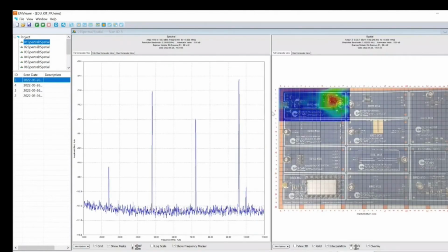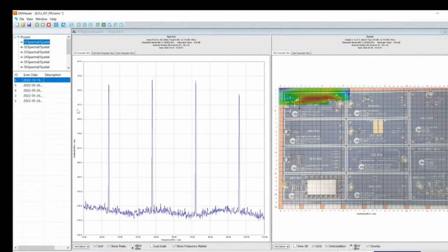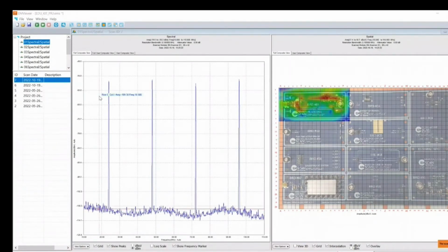And that's the software. This is the scan itself, that experiment that I did just before. Again, I can run the scan now, and you can see how it's working, and it's actually building and scanning it. Now I'm going to change the location of the marker of the jumpers to eliminate the big current return loop, and I'll scan again, and you can see, of course, that everything changed here.